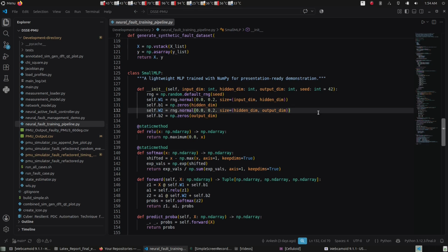So I'll reiterate again, the idea was to first find the fault, any fault. If there is an anomaly in the circuit, it will be recorded. If there is a sudden change in the phase, it will be recorded. If there is a gradual shift in the phase, even that will be recorded. So all kinds of anomalies that happen when the ideal waveform is not present. We have provided an ideal base scenario, that suppose this is my base scenario, if any deviation from this base scenario happens, then please record that scenario.